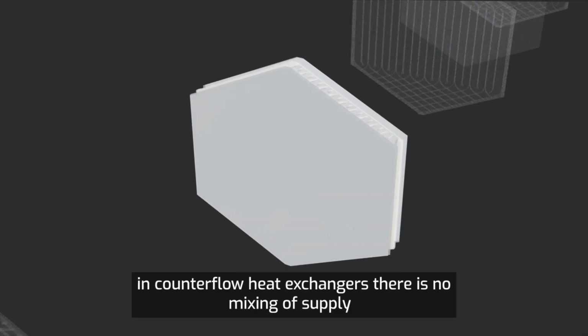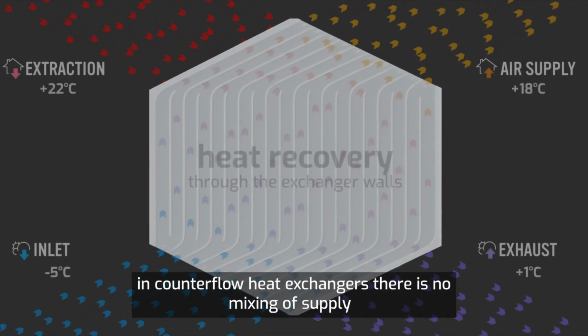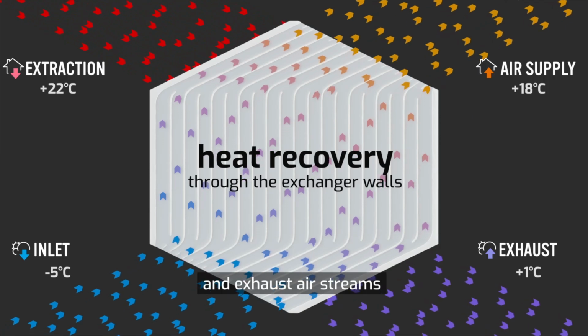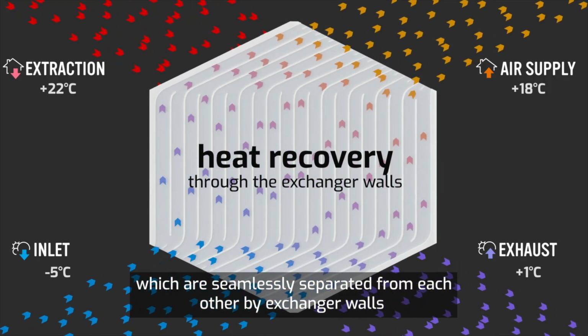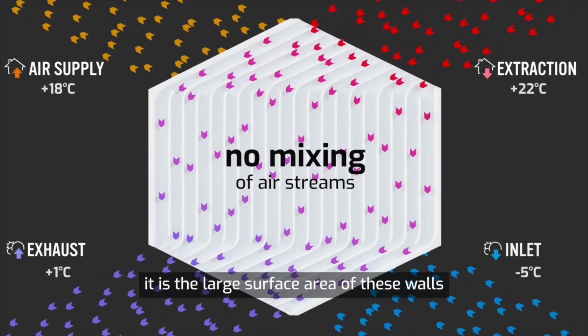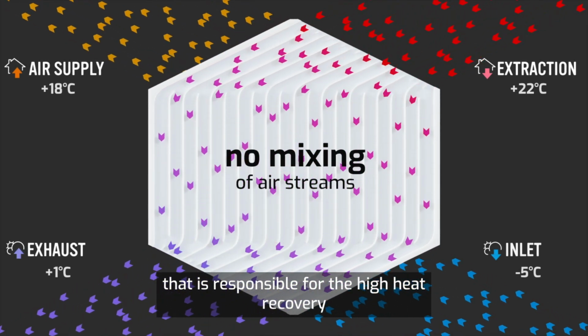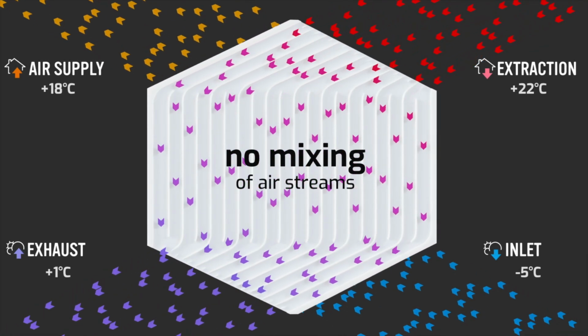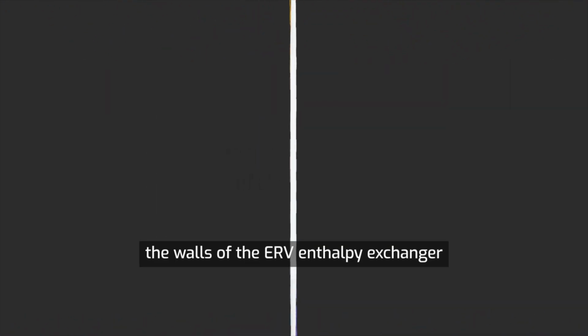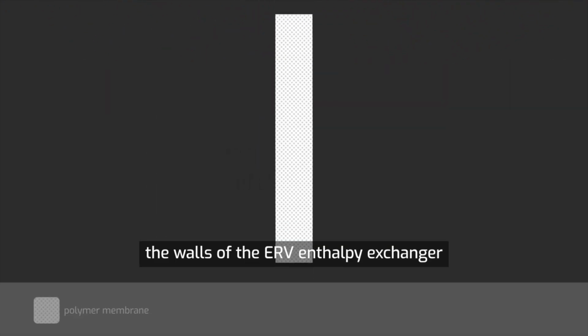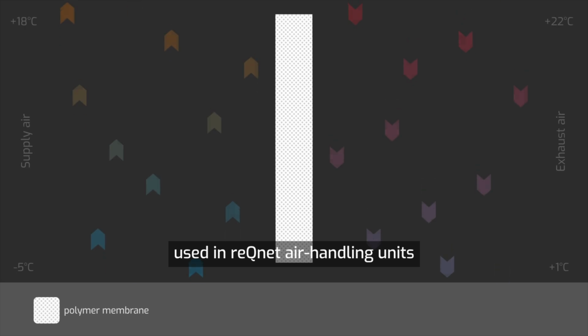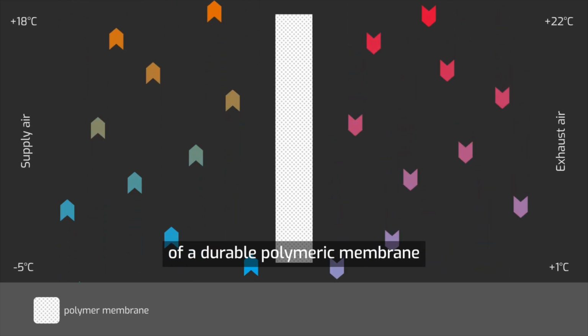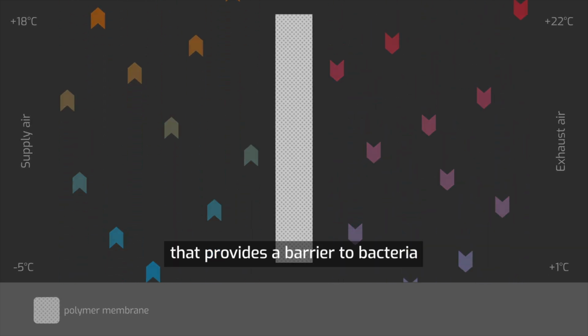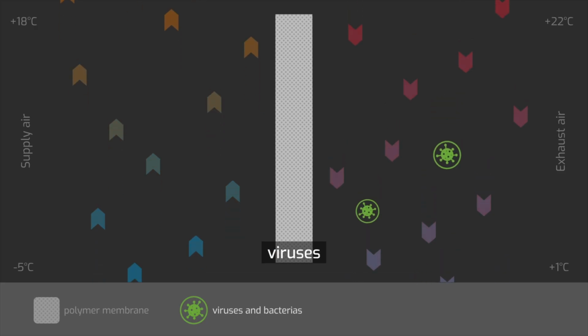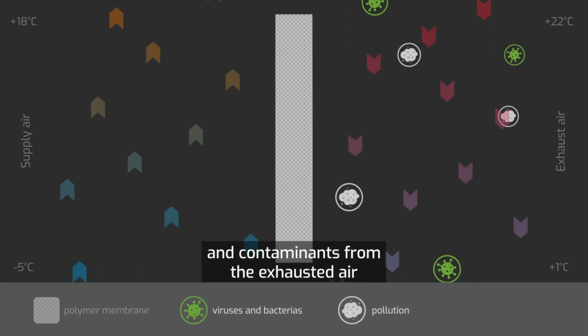In counterflow exchangers, there is no mixing of supply and exhaust air streams, which are seamlessly separated from each other by exchanger walls. It is the large surface area of these walls that is responsible for high heat recovery. The walls of the ERV enthalpy exchanger used in RetNet air handling units are made of a durable polymeric membrane that provides a barrier to bacteria, viruses, and contaminants from the exhausted air.